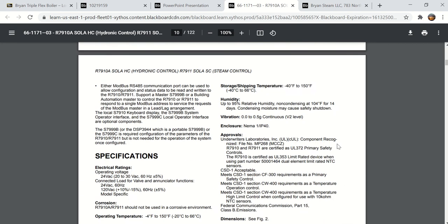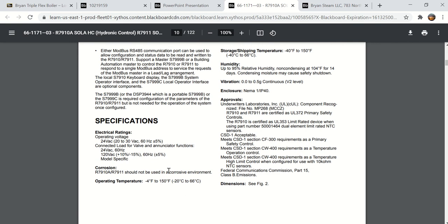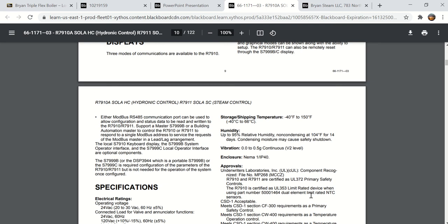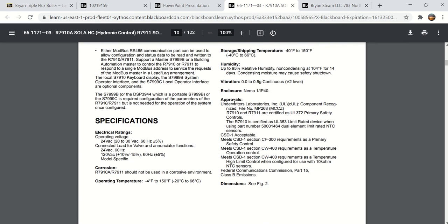I want to get down here to the specifications. This is very important information. You see here where it says approvals, Underwriters Laboratory, CSD1. CSD1 is something that you definitely need to understand or know what that means. Underwriters Laboratory, UL listed. Anytime you see UL listed on electrical components, you know that it has met certain standards. But the CSD1 standard is a controls and safety device standard for boilers, and it's important to know that.